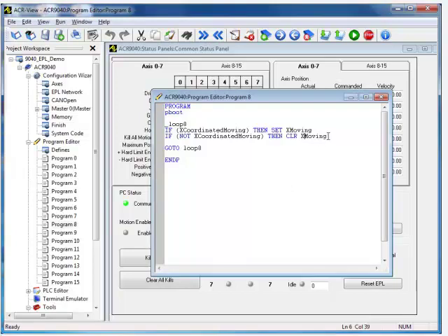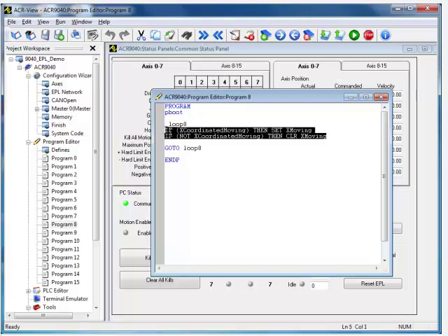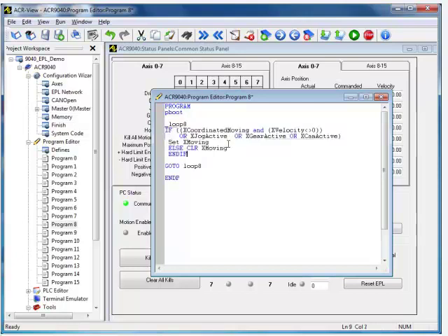If you were to do a jog move, gear move, or cam move on X, it'd be moving, so you'd want to check if any other moves were going on, and if you only wanted the output to be on when X is actually moving. Instead of this simple little program, we'd want to check for a couple other conditions.